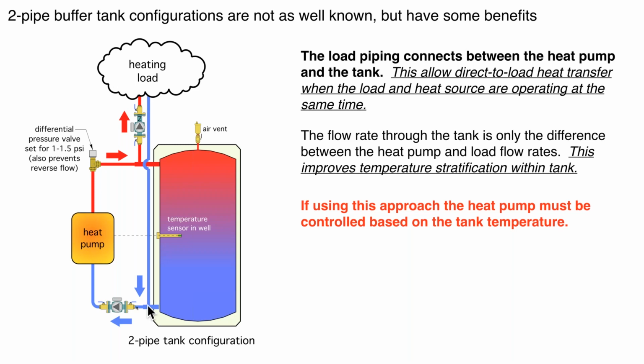What can happen is some of that water is going to go this way without this device in place, okay? And some of you may be thinking, well, I'll just use a circulator with one of those built-in check valves. Well, those built-in check valves can only hold back at most about half a PSI. And in some cases, if you have high flow rates here, you might actually build up more than half a PSI differential between this T and this T, and that is going to overpower the spring in that check valve, and it's going to send some of that water up through the heat pump. Now, that doesn't hurt the heat pump. It doesn't hurt a boiler.